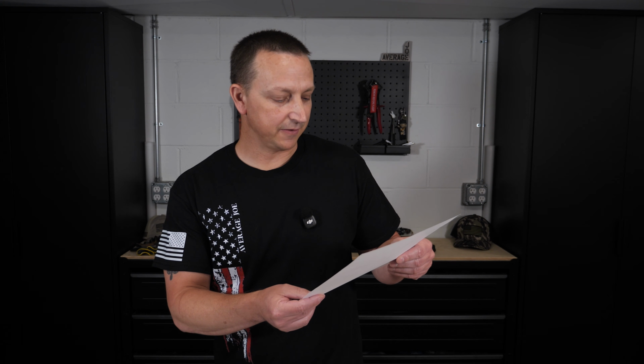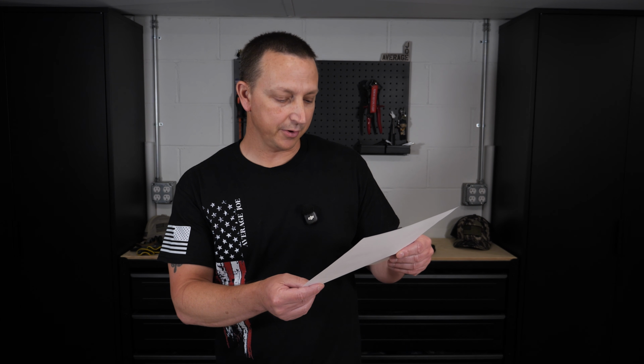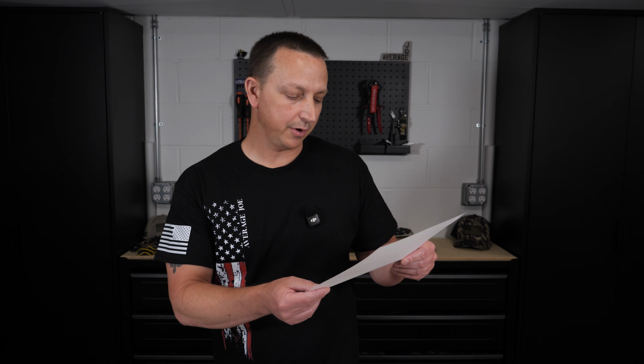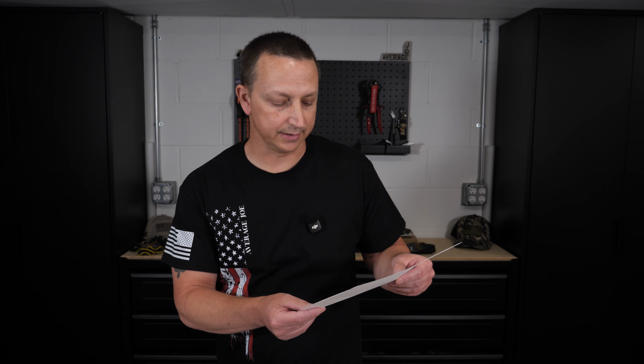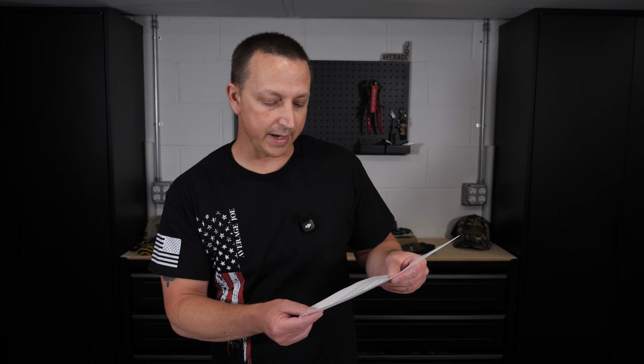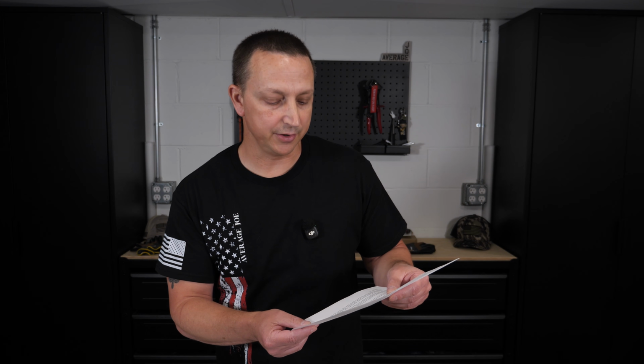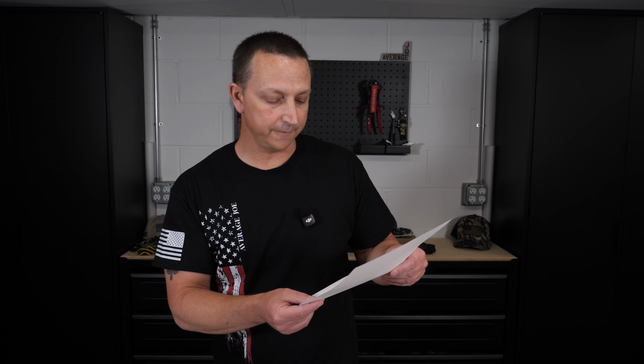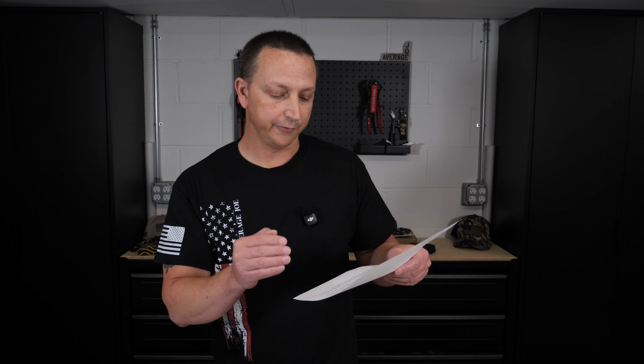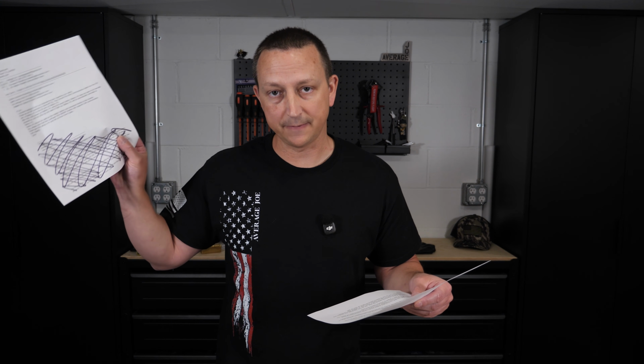The inverter must be configured with the correct BMS protocol, while the battery BMS will automatically match the protocol once properly connected, which we did. The battery directly connected to the inverter should be set as the master battery, while all additional batteries should be configured as slave units. Communication between batteries should be connected using the 485 out to 485 in, which is basically what we did last time and what they said in the last email.